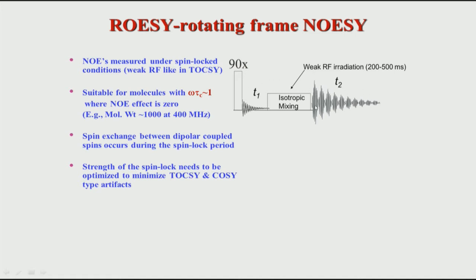In ROESY we do it in a different manner. Here we apply a 90-degree pulse, then allow spin A to evolve — the same approach as in TOCSY. Then we mix the magnetization by applying what is called a spin lock, which is a weak irradiation applied for a duration of 200 to 500 milliseconds. During this period, similar to what happens in NOESY, polarization from one spin is transferred to the second spin, which carries with it the information of the chemical shift during T1.